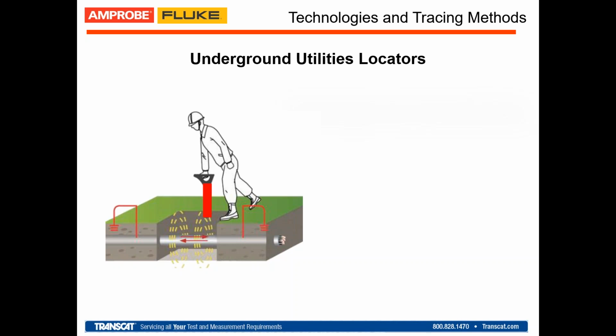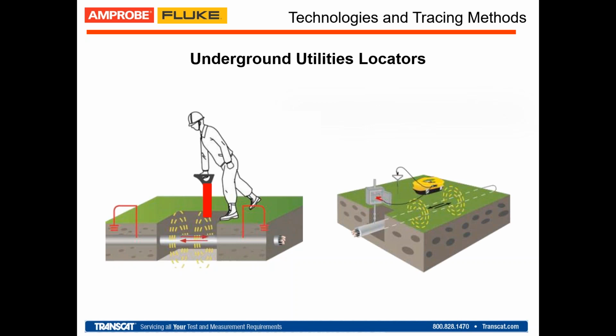The receiver has a sensor that perceives the electromagnetic field lines, and through firmware analysis provides the user with the location based on signal sensitivity, the direction, and the depth of the cable. In scenarios where the underground cable is not carrying any current, or is carrying DC current which is not detectable by the receiver, we need to find a way to inject a signal that can be perceived by the receiver.